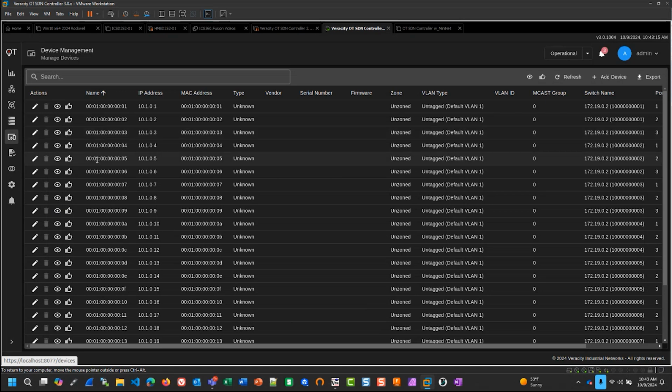Rockwell PLC, for example, we fingerprint that PLC. That means we know that it's this MAC address, this firmware revision, this serial number, although we don't use firmware in the fingerprint, this Rockwell product code. If we see that device come onto the network and all of those characteristics don't match what we know, the device is immediately quarantined. Maybe it comes on with a product code of 5 and it should have been 13, which would be a COM adapter. And it's scary that I know that. But it would automatically get quarantined.